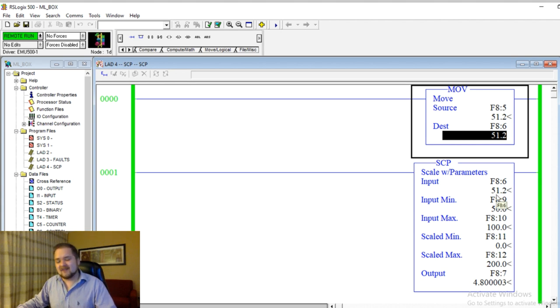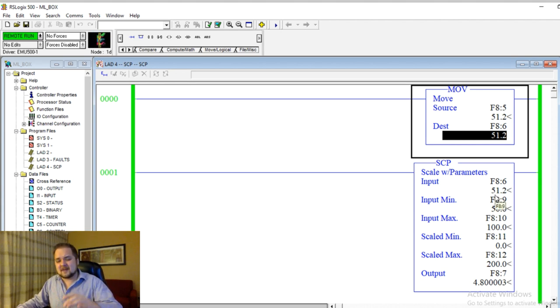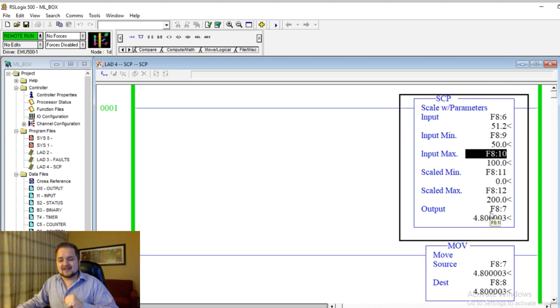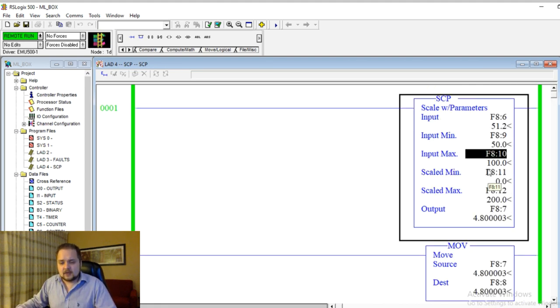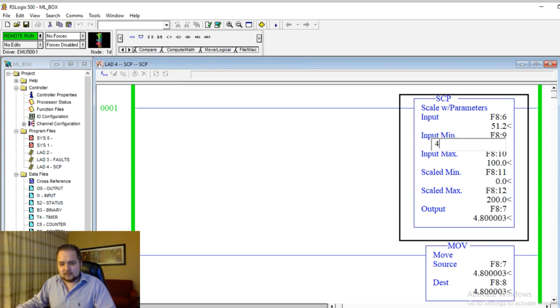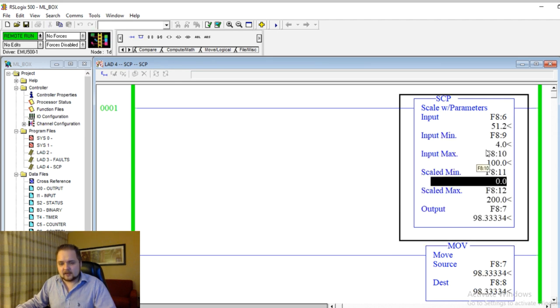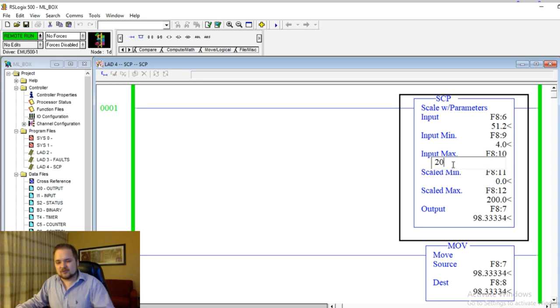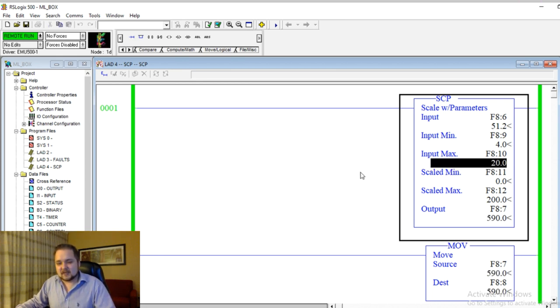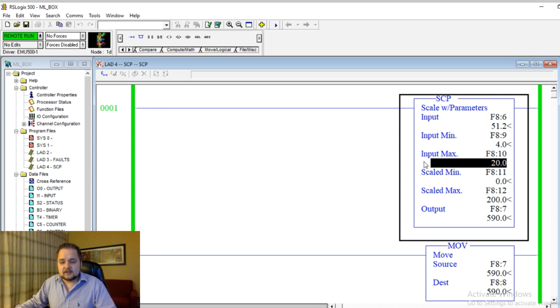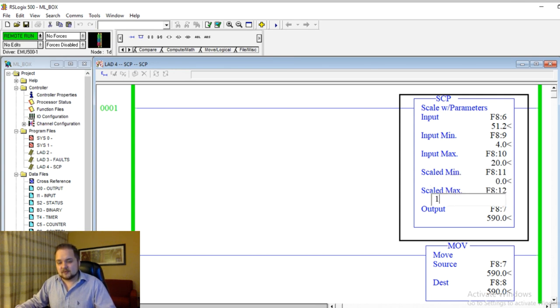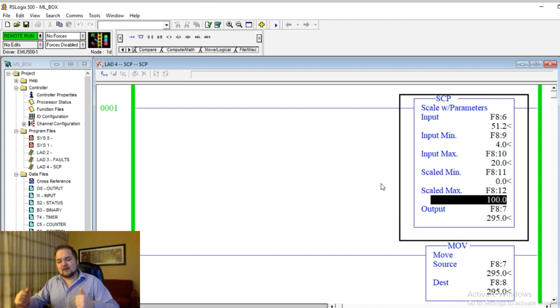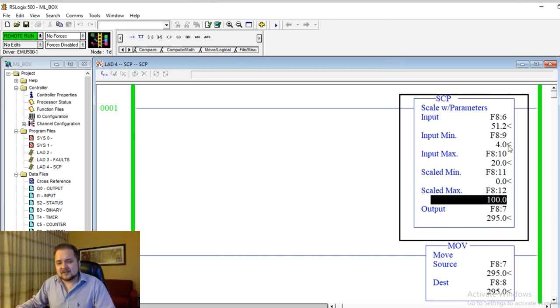And of course, you can have any combination with input mins and max, as well as the scaled min and max that you could extrapolate to. So the most common, for example, in analog, so 4 to 20, just something visual. So if you have a 4 to 20 signal coming in and you've scaled that correctly, then hopefully you get the right decimals, but then you can scale that from zero to 100. And that way you know exactly that you're getting the full range out of your flow meter.